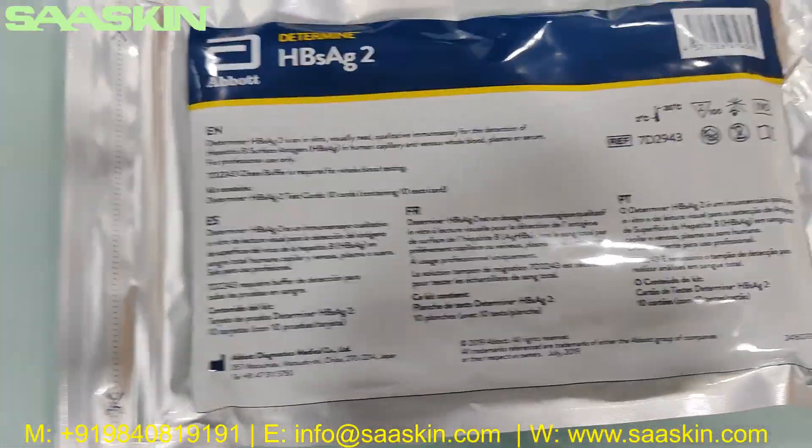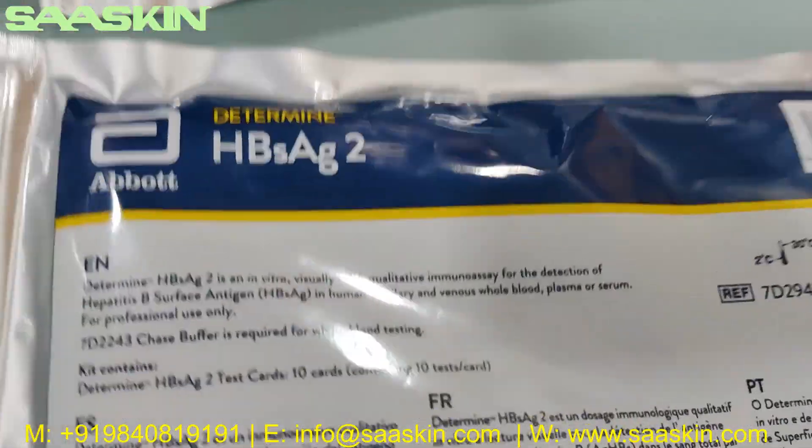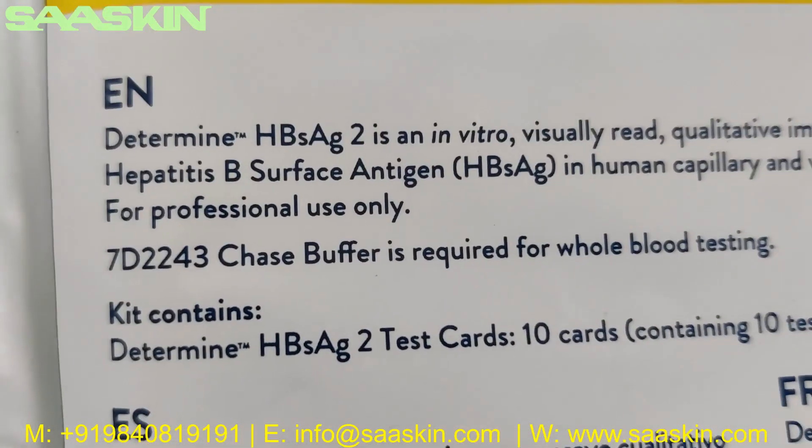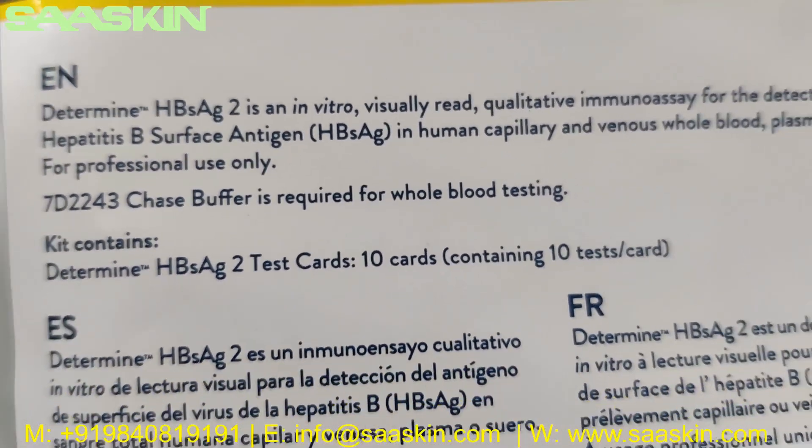Basically this is a test strip, and for using this one it is enough if you use plasma or serum. If you want to use whole blood, you need to have the chase buffer. The 7D2243 chase buffer is required for whole blood testing.